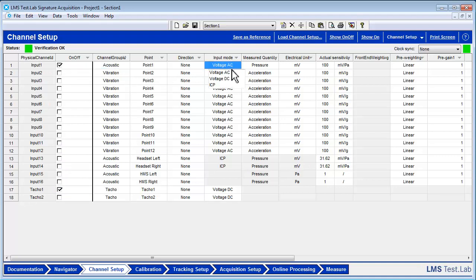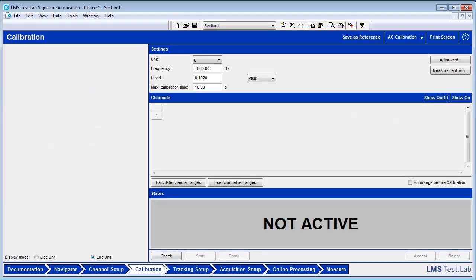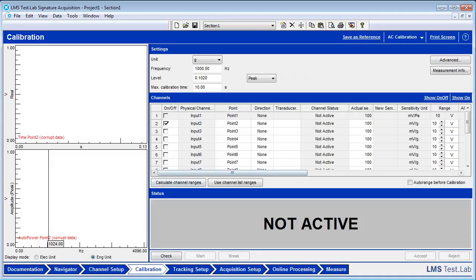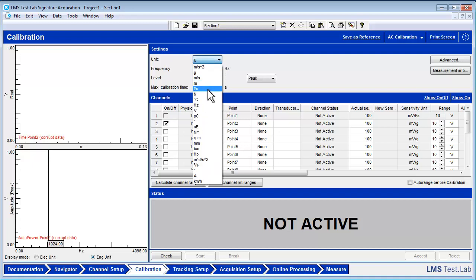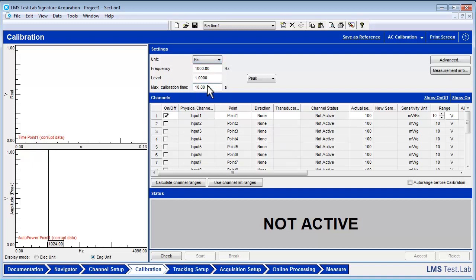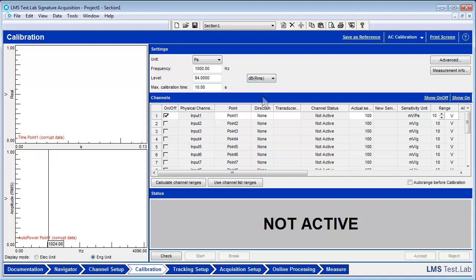In the Calibration Worksheet, we will calibrate the microphone. Change the unit to Pascals. Make sure that frequency is 1000 Hz and the level is 94 with dB RMS as units. These are the settings for this specific calibrator. Other calibrators may be different.